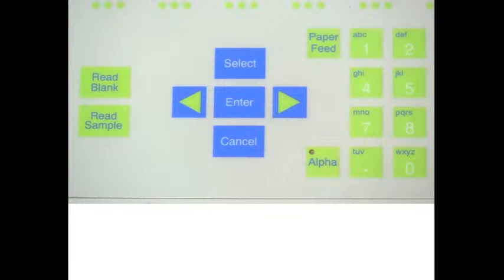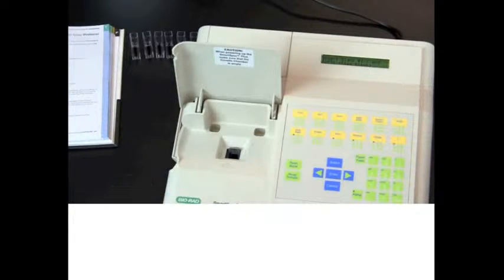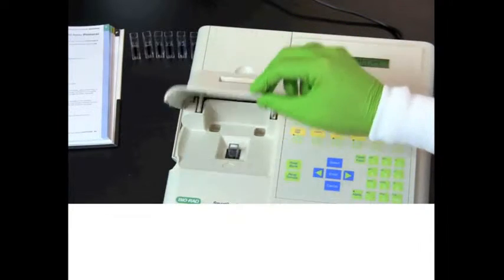To determine the protein concentration using a spectrophotometer, select the Bradford assay. When asked to insert blank into the spectrophotometer, insert the cuvette labeled control. Use the blank to set the spectrophotometer to 0 absorbance, or 100% transmittance. If instructed, read the absorbance of the 7 protein standards and record the absorbance values.